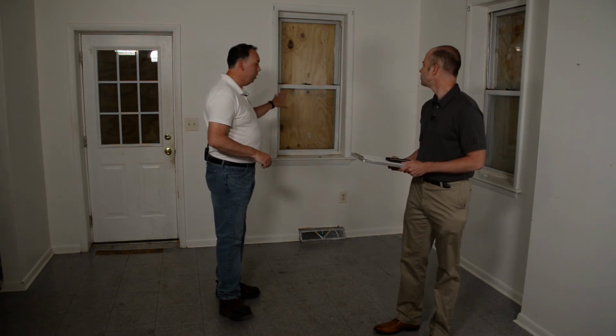Okay. And then also, could you just go over that 4% rule again, just so that everyone can understand what you talked about? Sure. So what we're talking about is the open window area, not the whole window. And so what you're going to do is basically measure the square footage of the floor of the room you're in, and then say it's 100 square feet. Well, you're going to multiply that by 4%. That's going to give you 4 feet. So you want to have at least 4 square feet of openable area for the ventilation for the room.